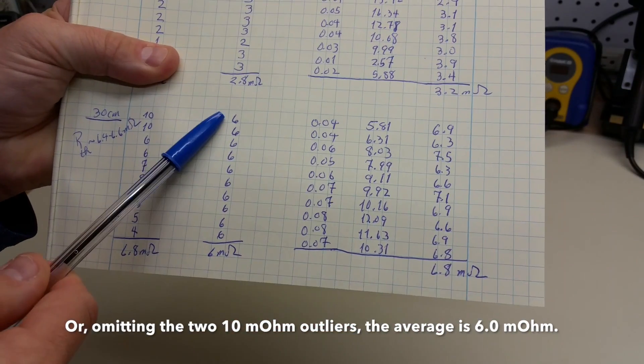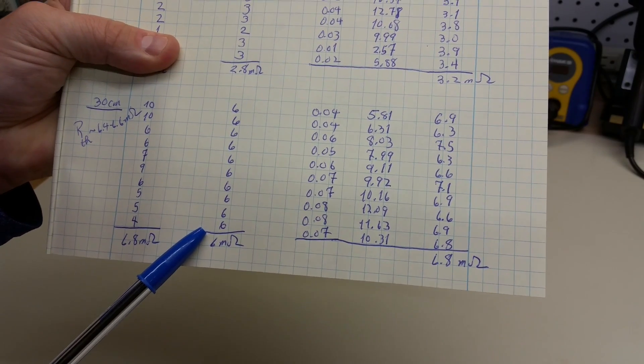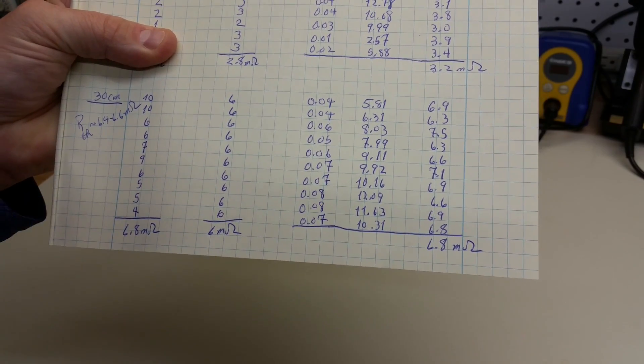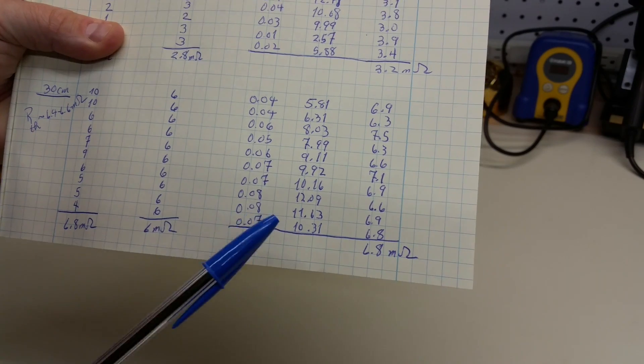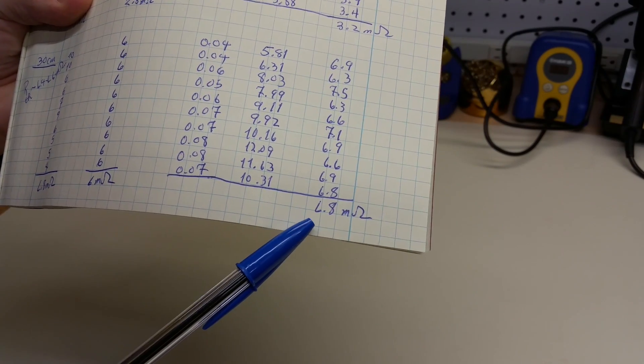The Kelvin clamp-based measurement, again, very stable, very steady. All of them are 6's, giving a 6 milliohms average. And then, the bench approach yielded an average of 6.8 milliohms as well.